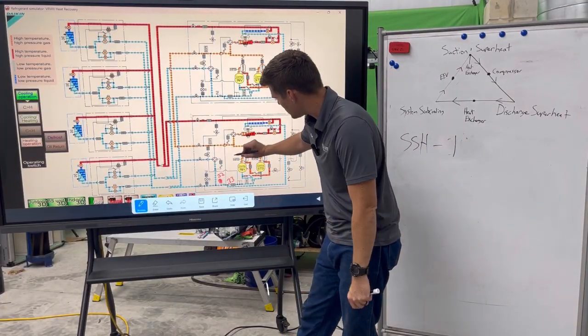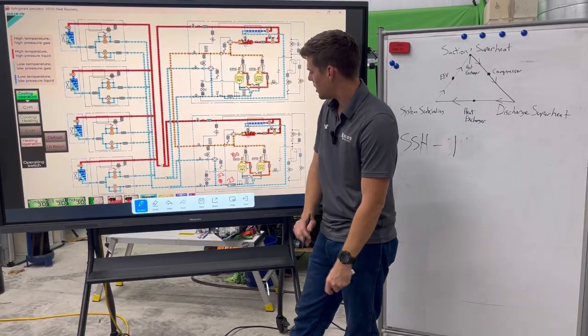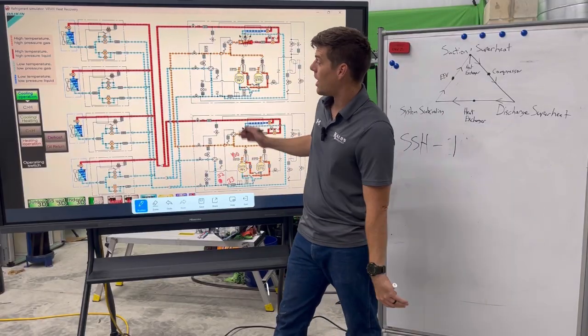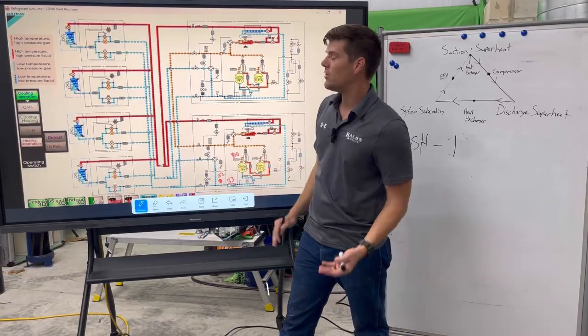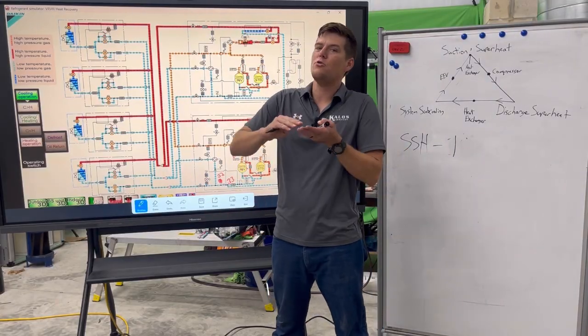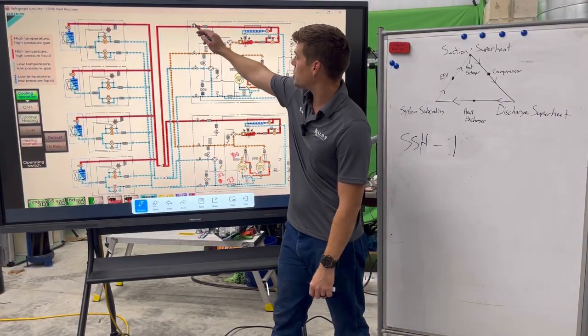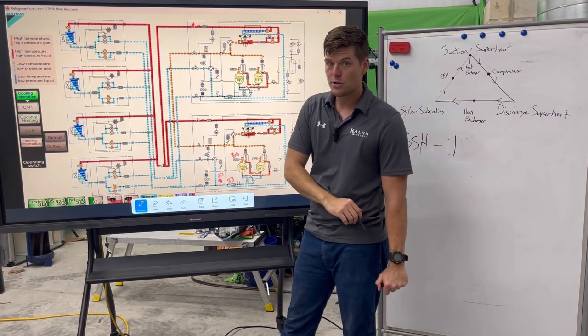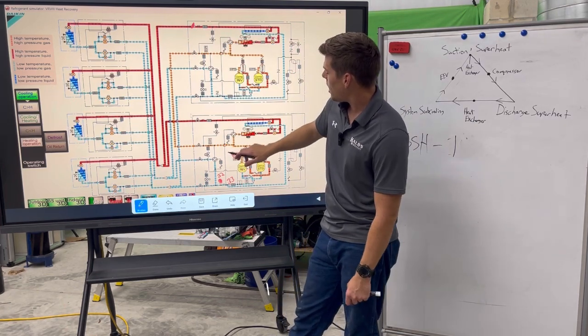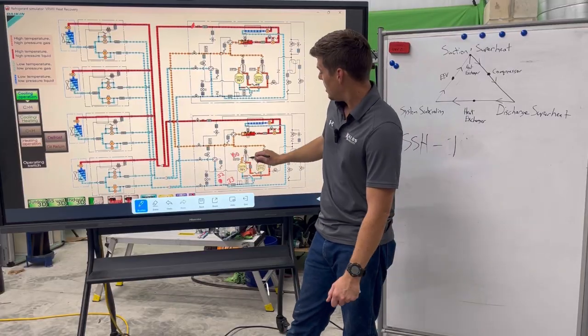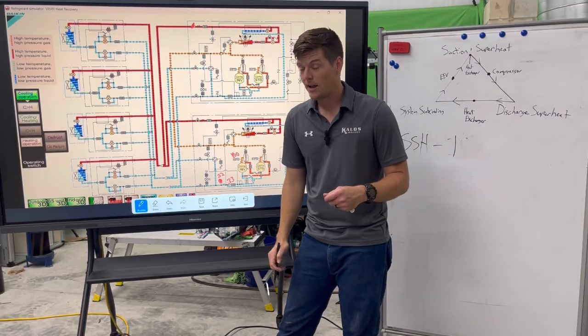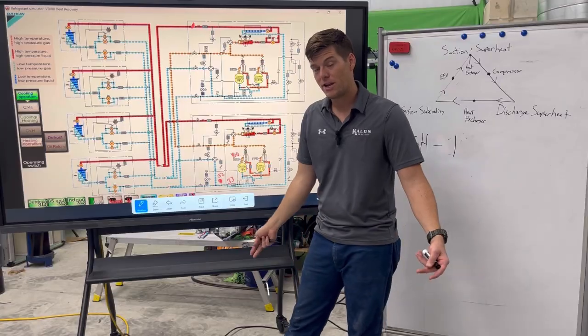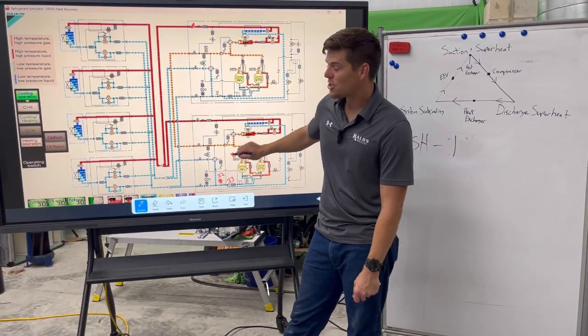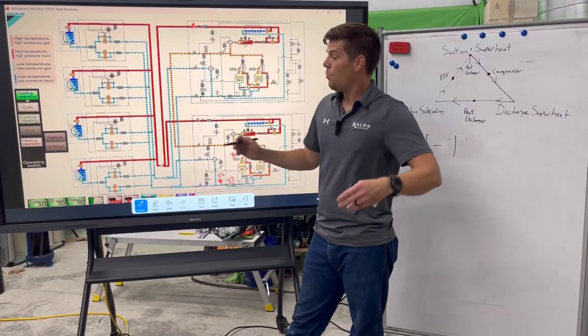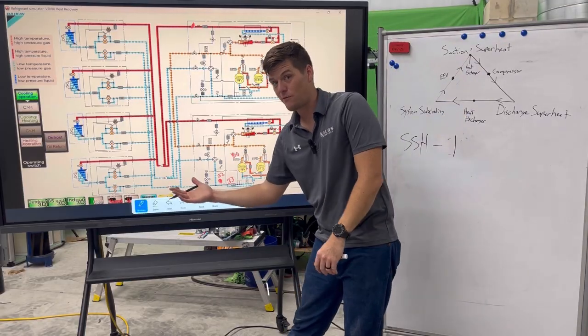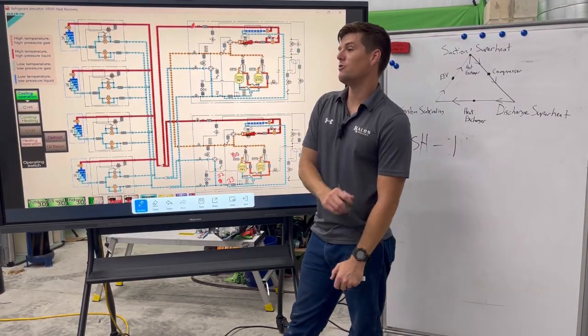Well, that high pressure sensor tells us the saturation temperature for my liquid line or my discharge line. Again, these lines are connected, liquid and discharge. There is a pressure differential between there, so you may see a few PSIs fall off from when you measure at your actual suction, your liquid connection and your discharge pressure. But for here, we're at 100 degrees of saturation. That means that the pressure here of 410A, because this is the refrigerant the system's operating with, the RV3 heat recovery, this 100 degree saturation temperature is telling me the pressure to saturation temperature for 410A. So my pressure is telling me it's 100 degrees saturation.